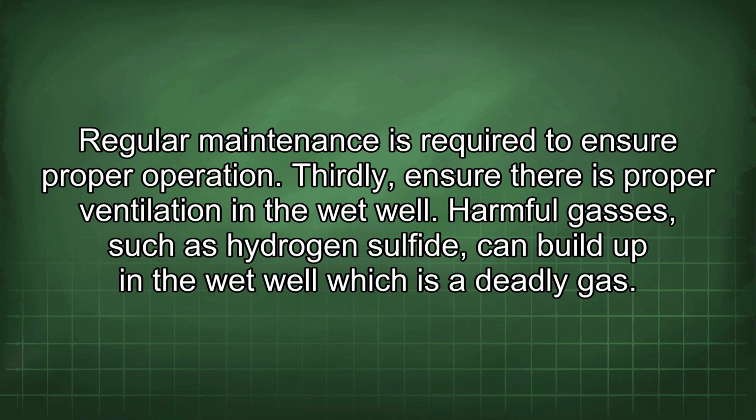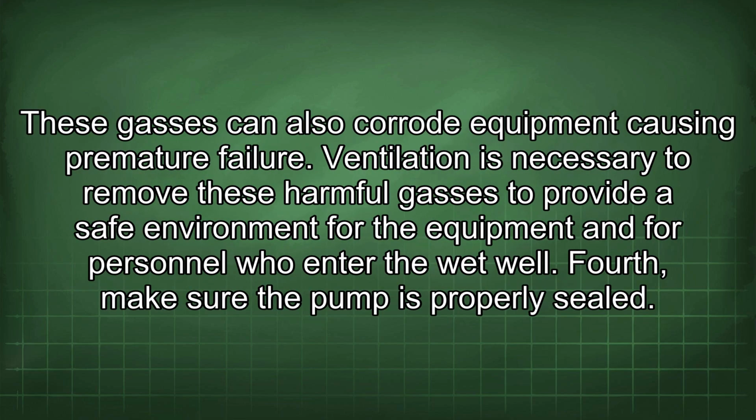Thirdly, ensure there is proper ventilation in the wet well. Harmful gases such as hydrogen sulfide can build up in the wet well, which is a deadly gas. These gases can also corrode equipment, causing premature failure. Ventilation is necessary to remove these harmful gases to provide a safe environment for the equipment and for personnel who enter the wet well.